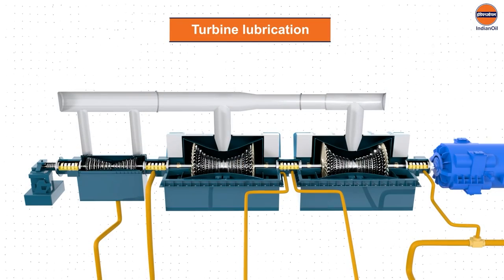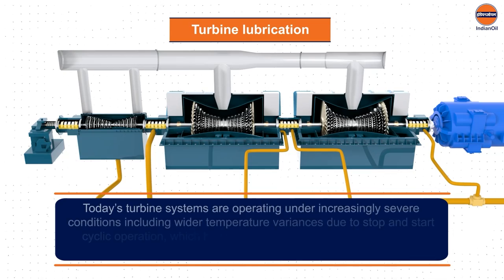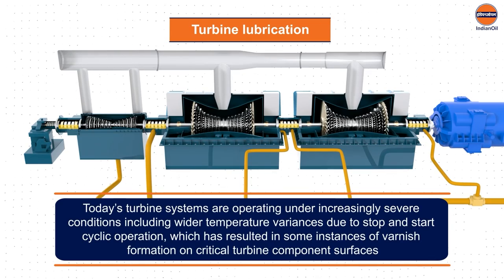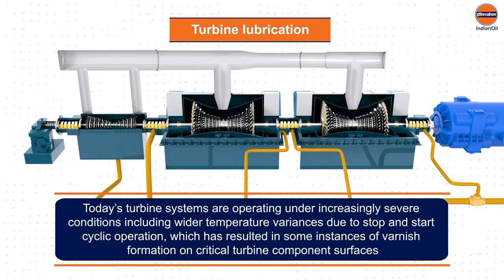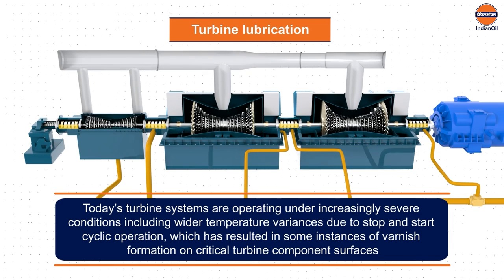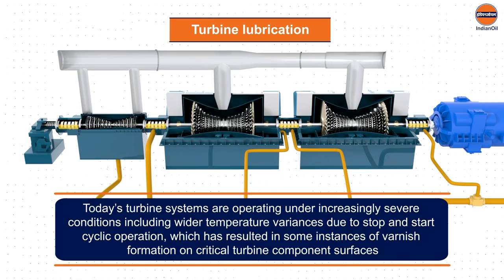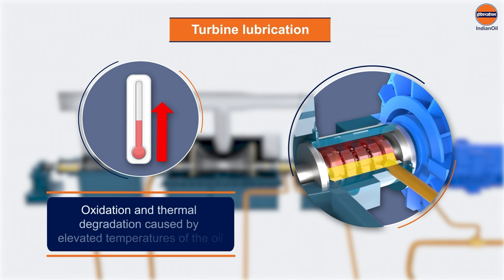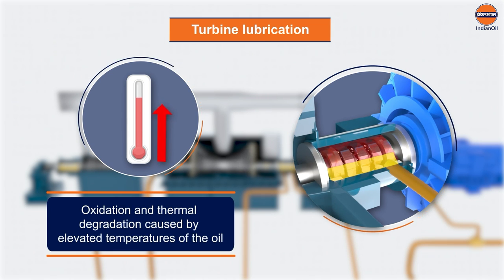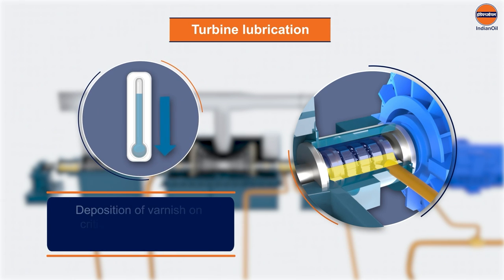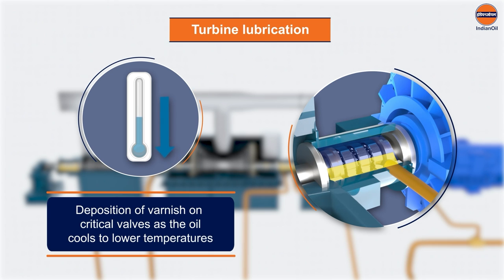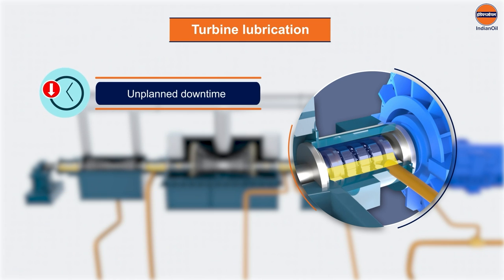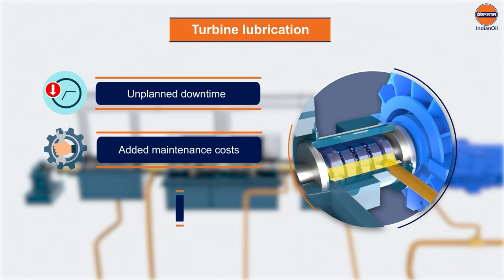To meet the ever-increasing demands for electricity, today's turbine systems are operating under increasingly severe conditions, including wider temperature variances due to stop-and-start cyclic operation, which has resulted in varnish formation on critical turbine component surfaces. Temperature fluctuation in turbine oil can result in oxidation and thermal degradation, initially caused by elevated temperatures, followed by the deposition of varnish on critical valves as the oil cools. Resulting stuck valves can cause unplanned downtime, added maintenance costs, and lower productivity.